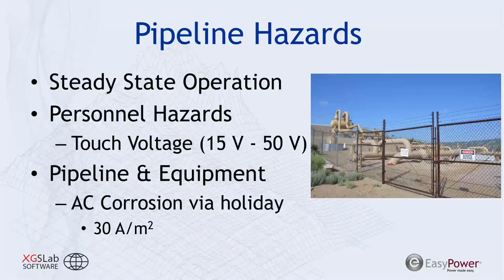And there's a phenomenon known as AC corrosion that if you have a slight defect in the pipe's coating, when you're having that induced current on that pipe, it can drastically accelerate the pipeline's corrosion. And that pipe that was supposed to last 50 years may not make it 5 because of this corrosion. The limits of that often vary depending upon the pipeline owner, but I know that they have observed AC corrosion as little as 30 amps per meter squared.